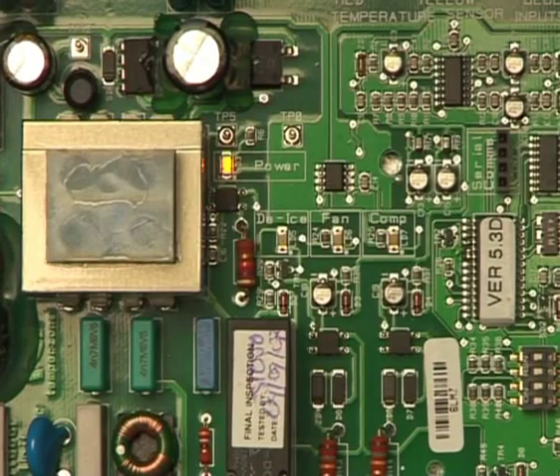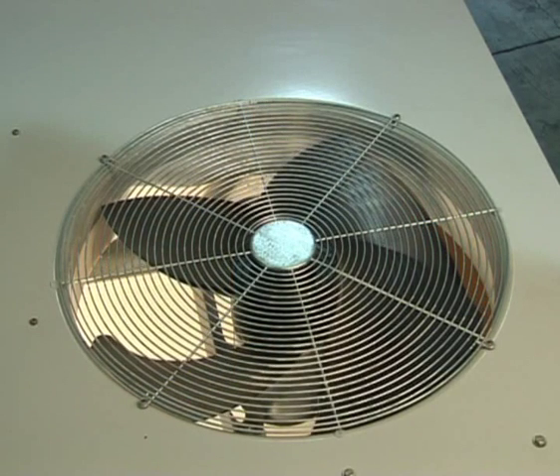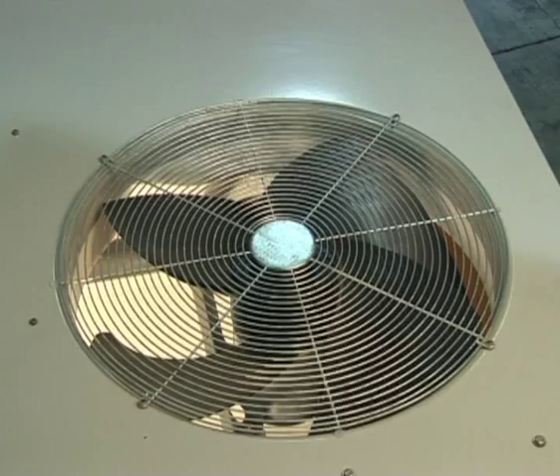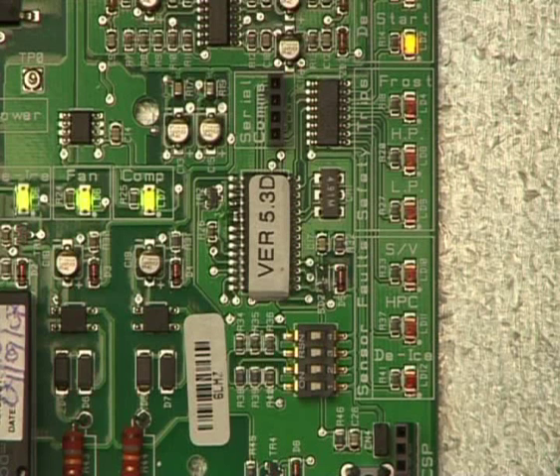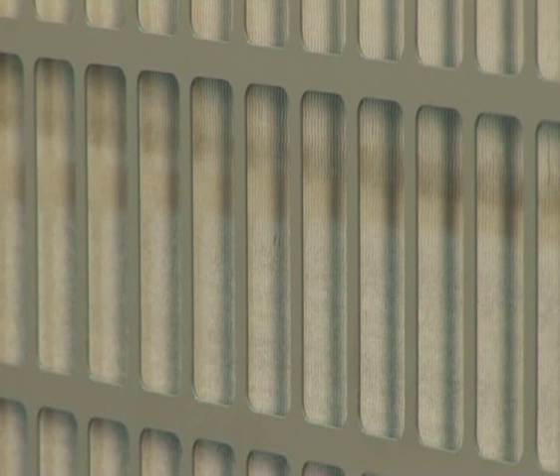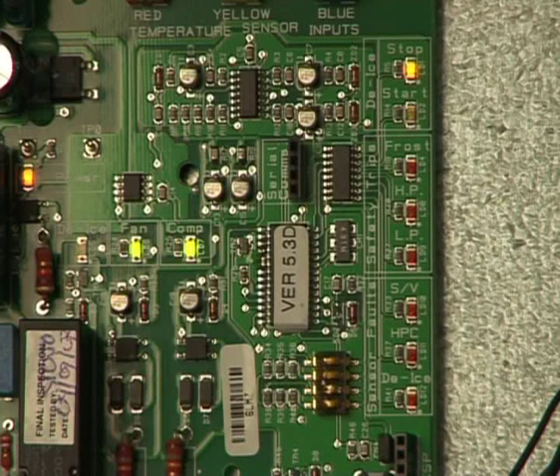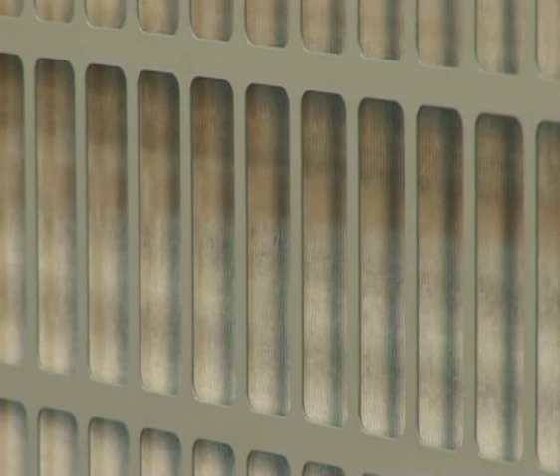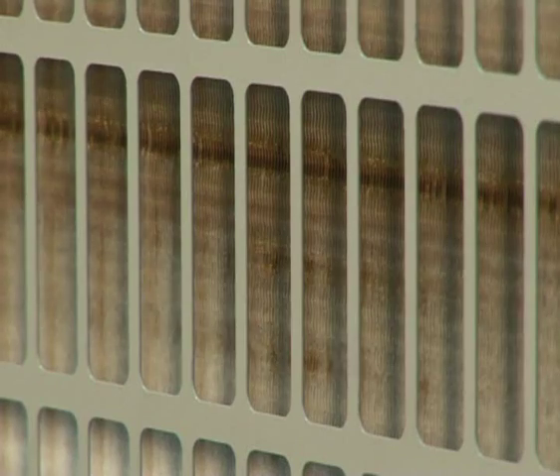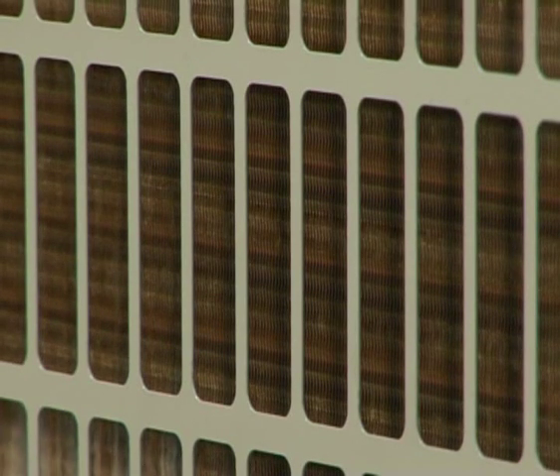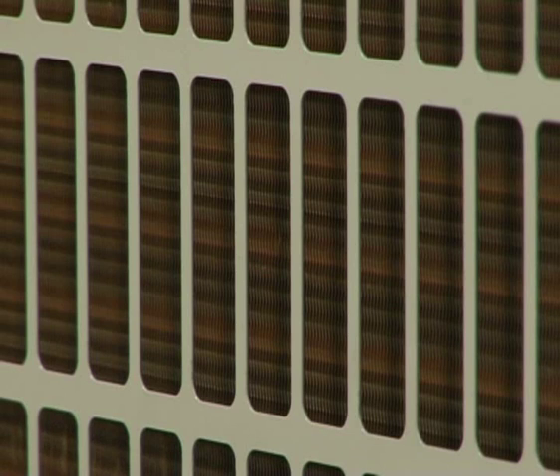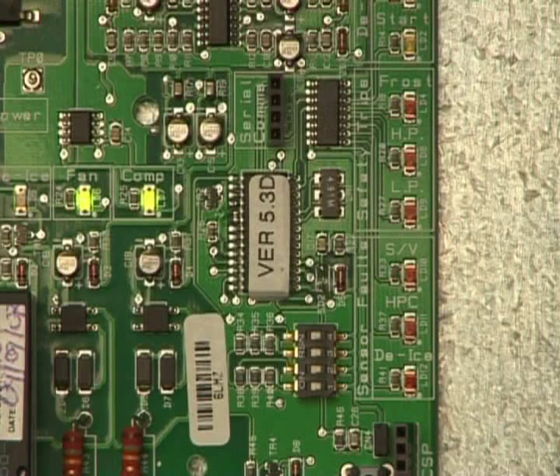The green de-ice LED will illuminate, indicating the de-ice cycle is operating. The compressor pauses at the start of every de-ice cycle. The outdoor fan stops, and during this pause, the reversing valve de-energises. The compressor then restarts and the de-icing commences. The de-ice start LED will go off as the temperature of the outdoor coil rises above the lower limit during the de-ice cycle. Eventually, the amber de-ice stop LED should illuminate, indicating coil temperature has reached the upper limit. The green de-ice LED will go off as de-ice terminates. The compressor pauses at the end of every de-ice cycle. During this pause, the reversing valve re-energises and the compressor and fans will restart. Normal heating operation is now resumed.